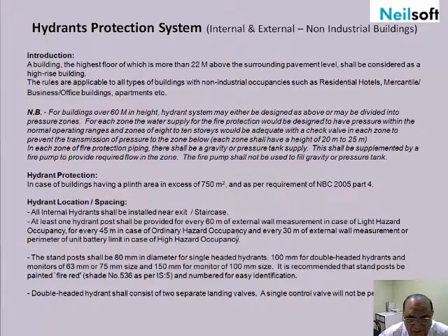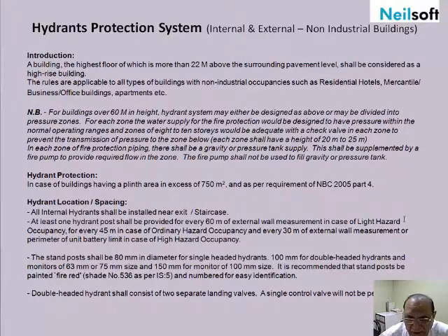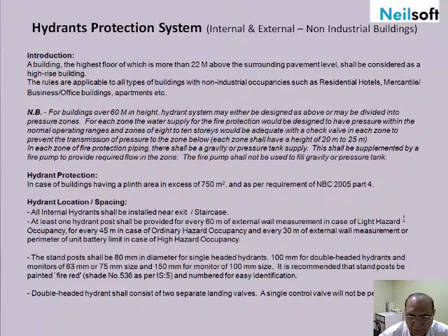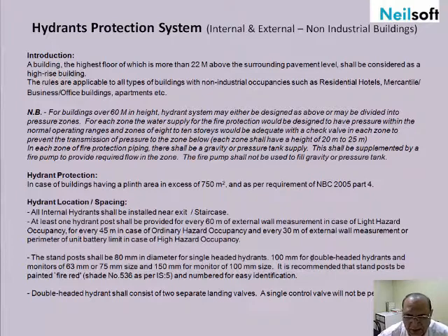At least one hydrant post shall be provided for every 60 meters of external wall measurement in the case of light hazard. For ordinary hazard occupancy, spacing should not exceed 45 meters. And for high hazard — generally industrial hazards or liquid fuels — hazardous materials should not be placed more than 30 meters spacing.